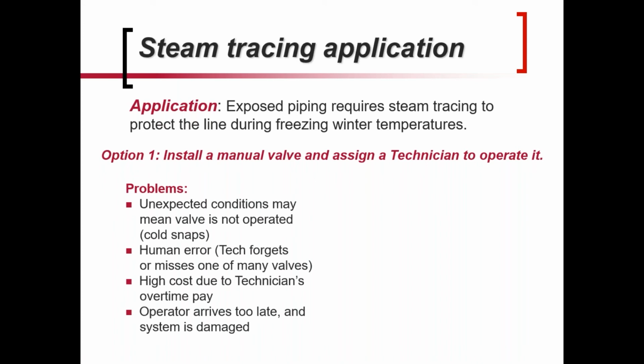An unexpected condition may mean that the valve's not open. So you have a cold snap in October, it goes down to 28, but no one opened the steam valve, and now you've got lines freezing. Not good. Human error, technician forgets or misses one of the steam trace valves. High cost, maybe there's overtime involved, that type of thing.